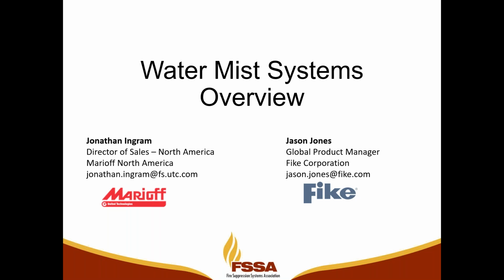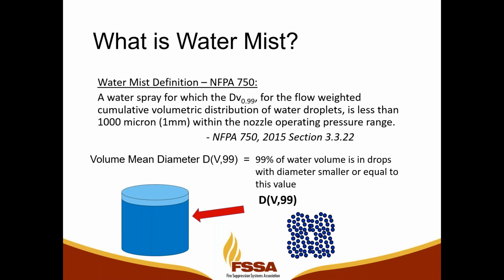Thanks, Todd. Okay, so first what we figured we'd do is talk about what is water mist. There's a lot of confusion in the marketplace about what is water mist. However, NFPA 750 pretty much defines what qualifies as a water mist type system. The first paragraph that you see on your screen really is the definition that you will find in NFPA 750 section 3.3.2 or 3.3.22. However, to put it in layman's terms, what this really means is that 99% of the water droplets discharged from the water mist head actually have to be under 1,000 microns to be considered a water mist system.